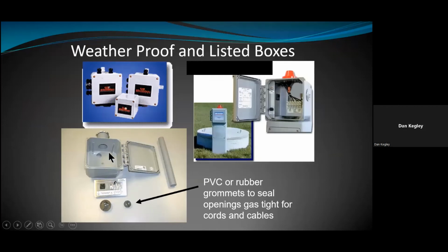So in this particular pre-manufactured pump housing junction box, the high voltage is on the back side of this plate feeding this receptacle, and on the front side of this plate is where you have these low voltage terminals. So this plate is providing that separation between the line voltage and the low voltage sides. They're not on the same side. The receptacle's on this side, but the connections and terminations are on the opposite side of this plate.